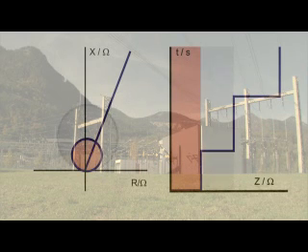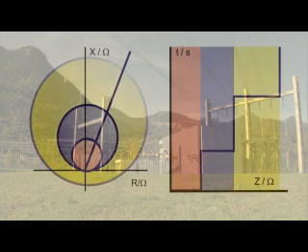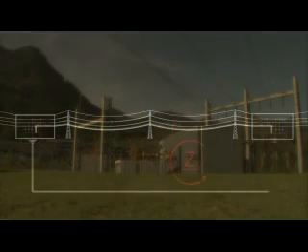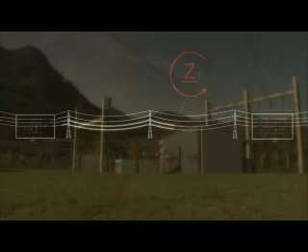These relays identify the zone in which the fault occurs by measuring the impedance of the fault loop and comparing it with the impedance represented by the zone setting. Since the impedance of the ground differs from the impedance of the conductors, the relay must apply a correction factor to determine the distance of a ground fault from the relay.